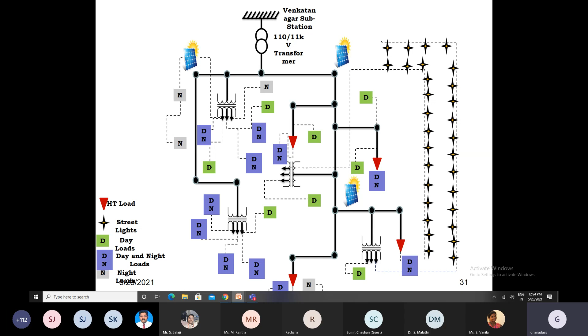This is another feeder - we have the layout of another practical feeder taken into account here. These star points represent where the transformers are connected. Using this current feeder, we determine where to connect the solar and how the inertia is calculated. That feeder is transformed into a one-line diagram.